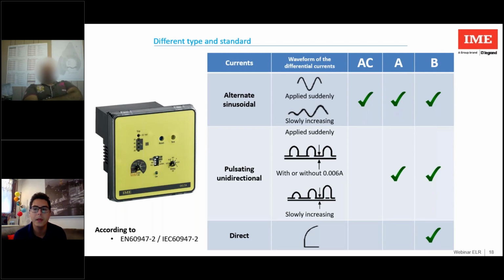The type AC is capable of reading sinusoidal waveforms with only alternating components. Adding loads that operate on pulses, such as a welding machine, adds unidirectional pulsating current. The type A is able to trip if these differential currents are detected. If instead we have a large server room where a capacitor can contribute with a direct current, here I need a type B.